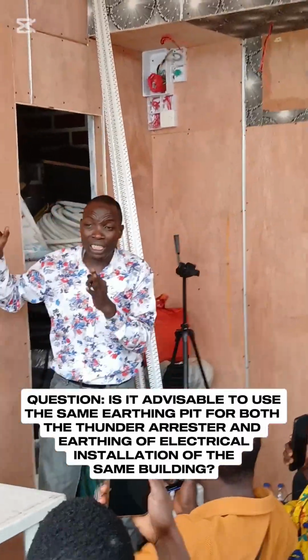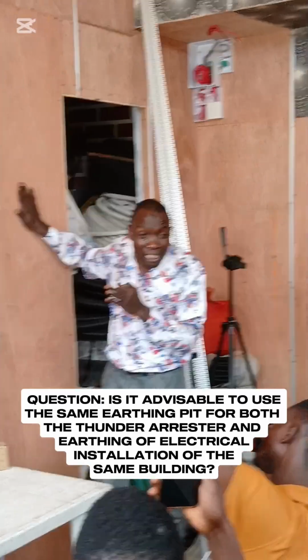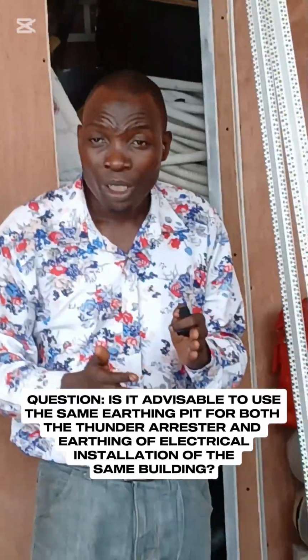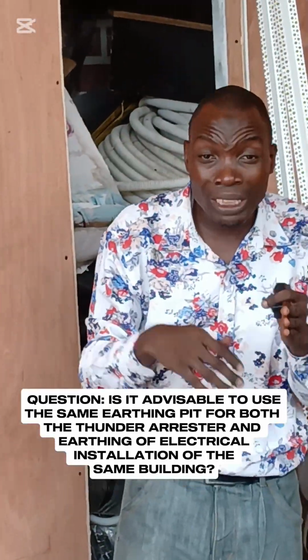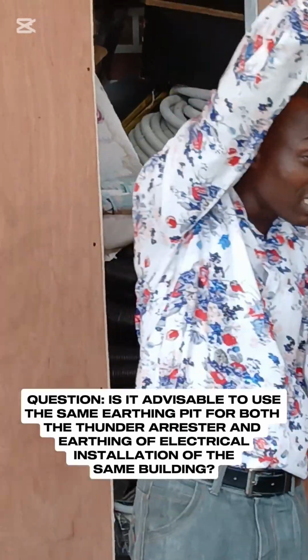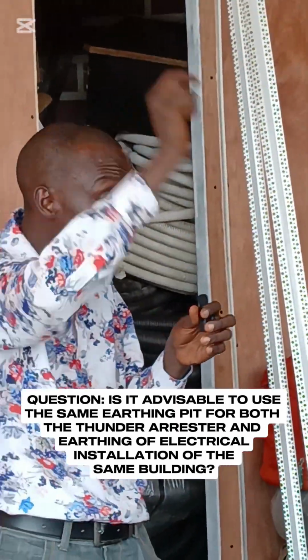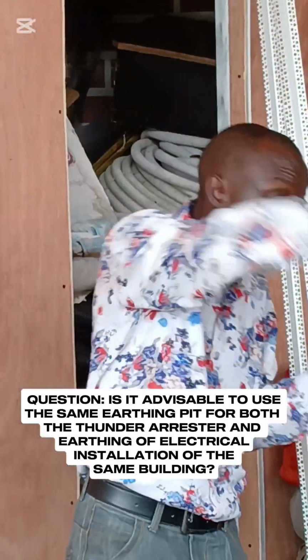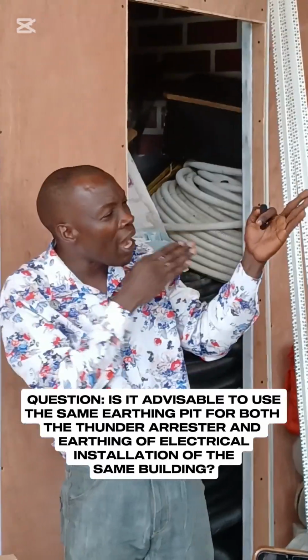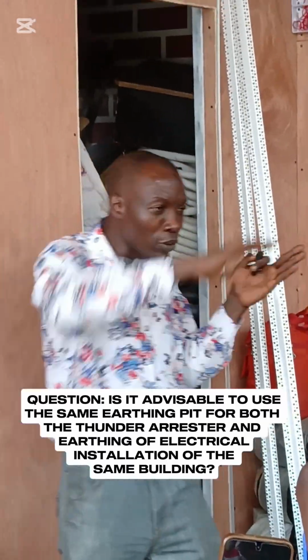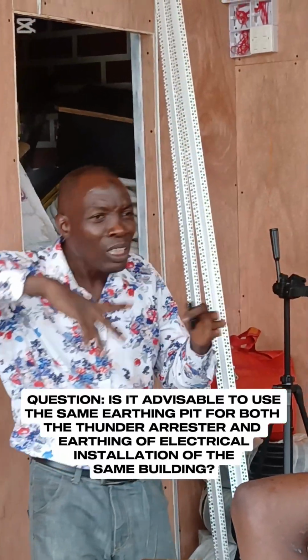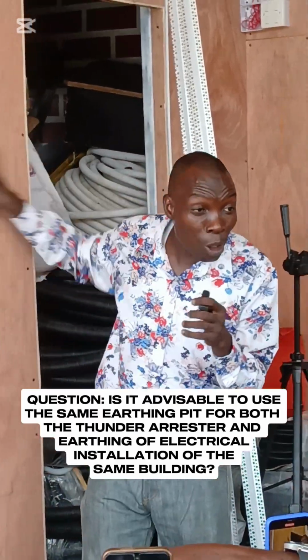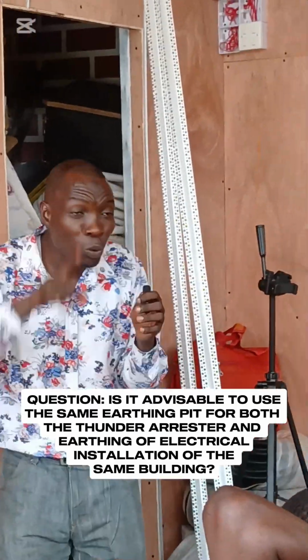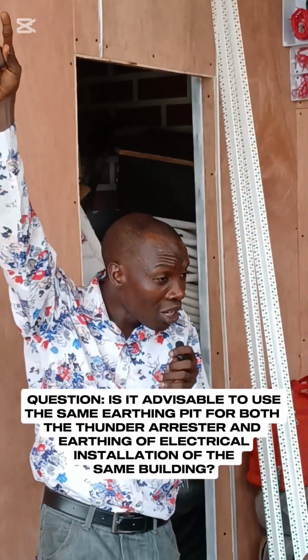You want to earth your thunder arrestor, you are protecting the building. It also depends on location. If your house is a bungalow but positioned in a very hilly place - there are some houses that keep getting thunder strikes time to time - it is because it is positioned on the path of the thunder, because of its location. So in that case, you are going to protect that building. The structure of that building is where you attach the thunder arrestor and ground it.